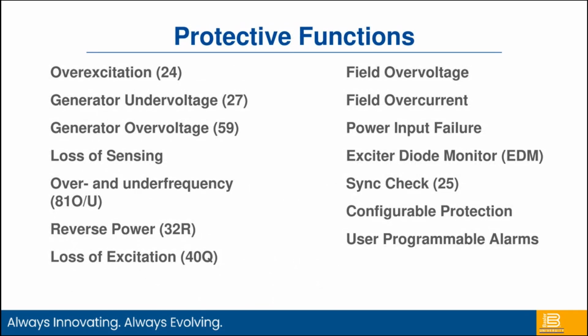And again, since we're monitoring all the different parameters throughout the generator, we can add protective elements, not just what a voltage regulator is looking at, such as the field itself or the diodes or the things we've already talked about, but we can also do reverse power, over/under voltage, over/under frequency. Multiple other protective functions can be incorporated.